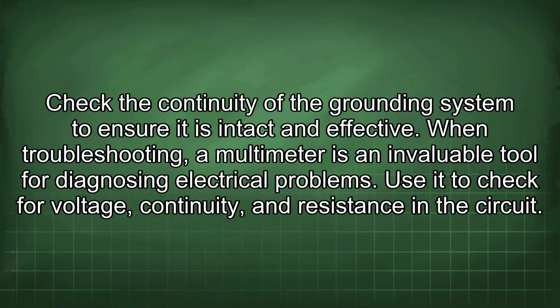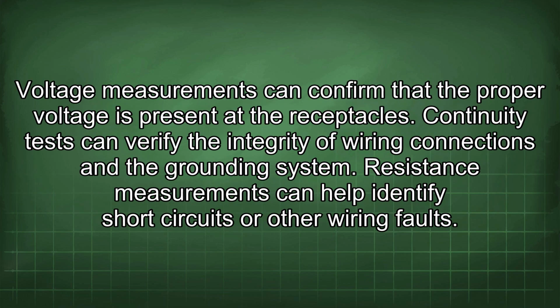Check the continuity of the grounding system to ensure it is intact and effective. When troubleshooting, a multimeter is an invaluable tool for diagnosing electrical problems. Use it to check for voltage, continuity, and resistance in the circuit. Voltage measurements can confirm that the proper voltage is present at the receptacles. Continuity tests can verify the integrity of wiring connections and the grounding system. Resistance measurements can help identify short circuits or other wiring faults.